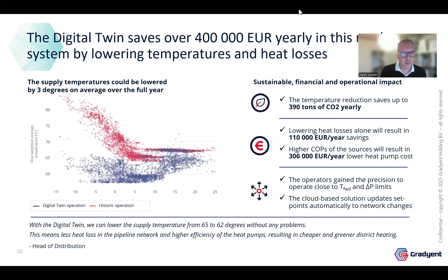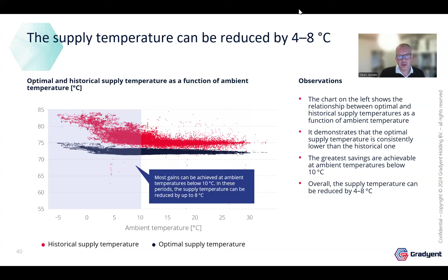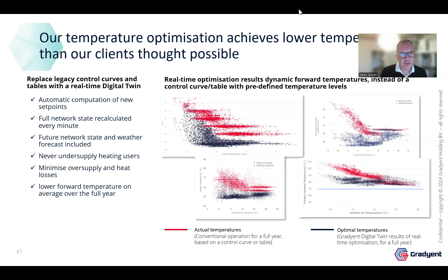This gives savings on heat losses, and it gives the opportunity to improve the COP of the heat pumps because we can lower both supply and return temperatures. That goes across all our systems. Here's an example where we were actually able to lower 8-10 degrees. That's not unusual, and when we look across all our different systems in operation, this is the typical case, benefiting the heat loss but also benefiting temperature-sensitive heat sources like heat pumps.